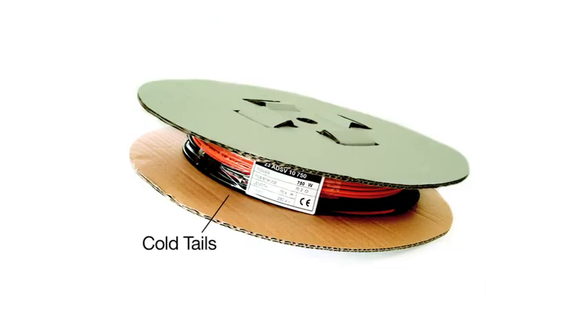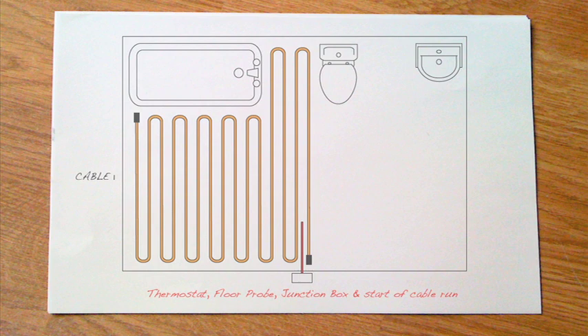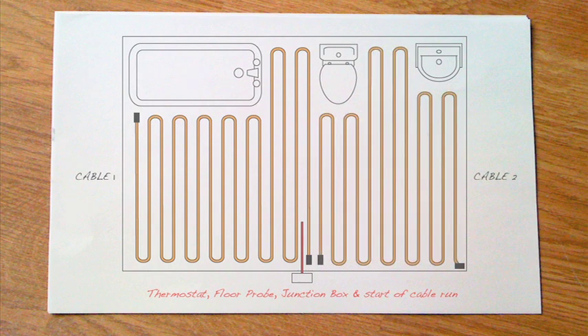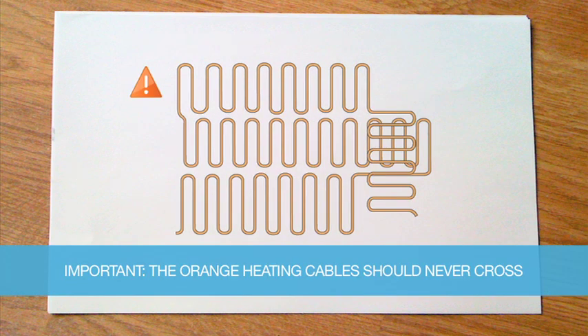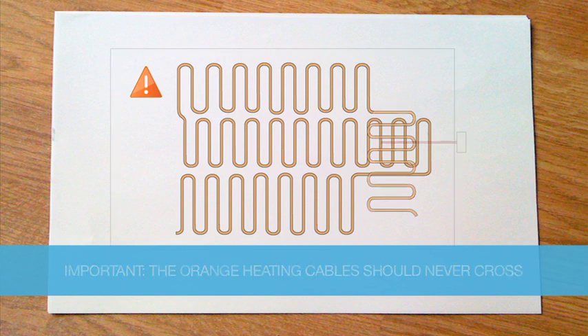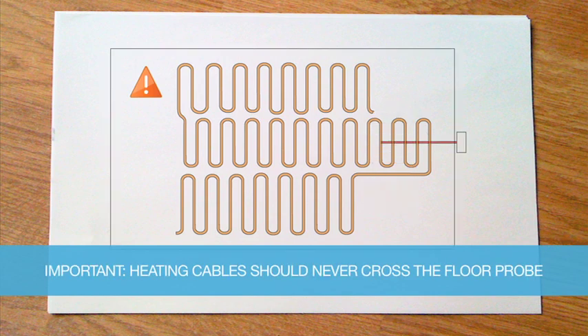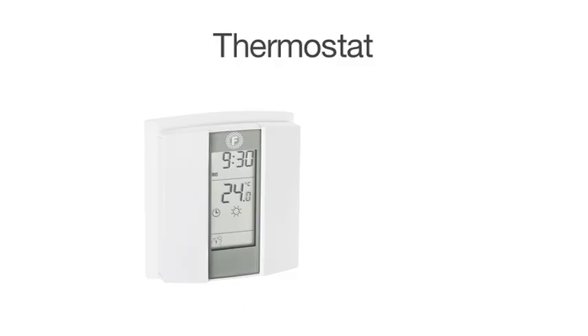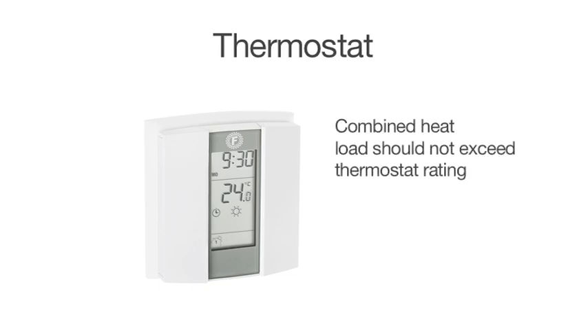Plan your installation so that all cable cold tails, the black power cables, terminate in one junction box. Multiple cables are joined in parallel. The orange heating cable should never cross at any point. Heating cables should never cross over the floor probe. A single thermostat can be installed to control multiple heating cables. However, the combined heat load should never exceed the rating of the thermostat. If this does occur, a suitably rated contactor should be installed.